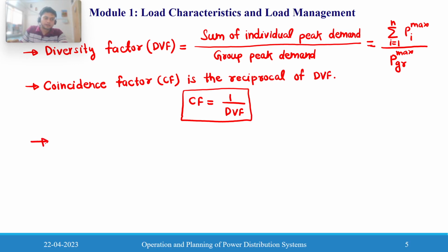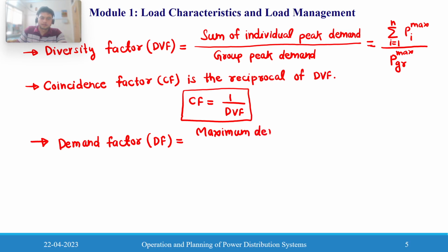The third important term is the demand factor. It is the ratio of maximum demand to the total connected load.